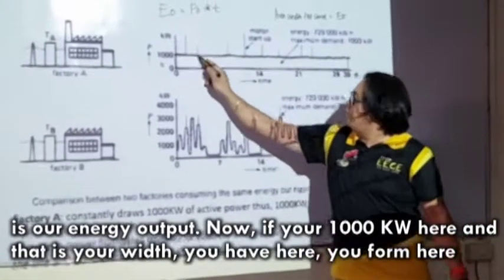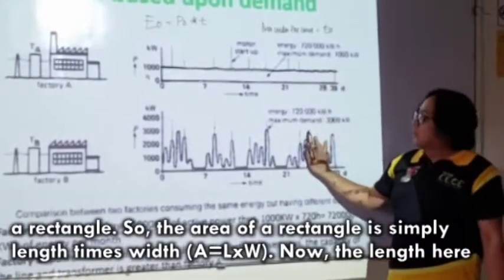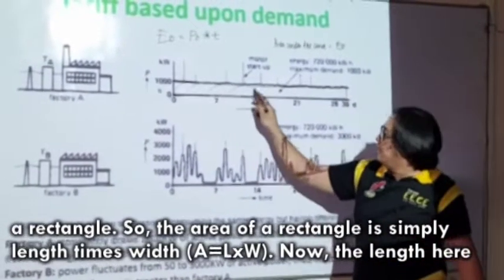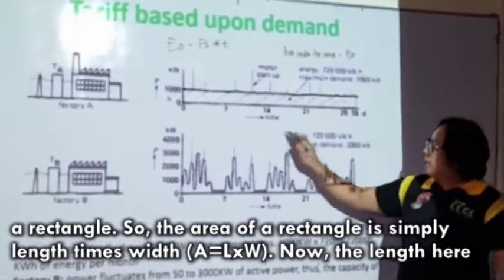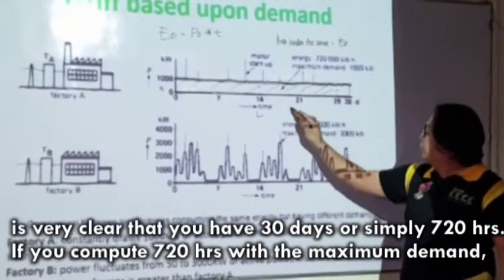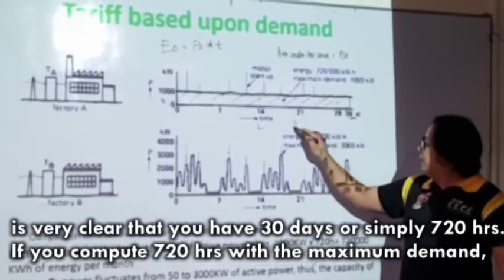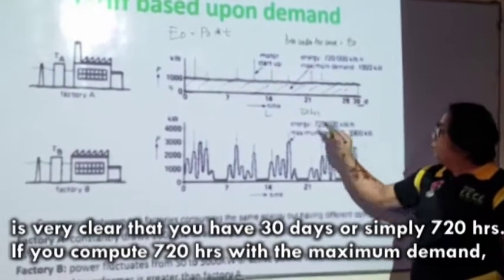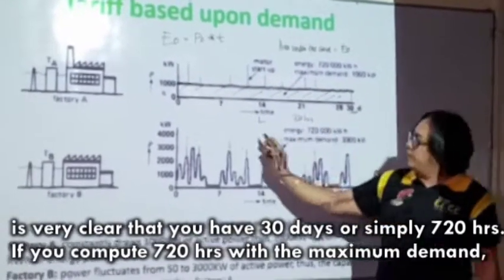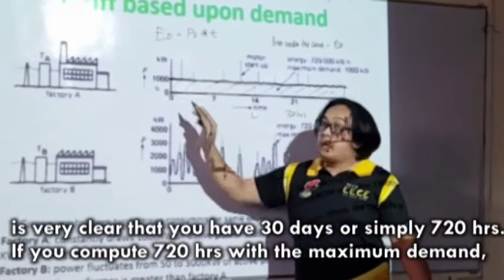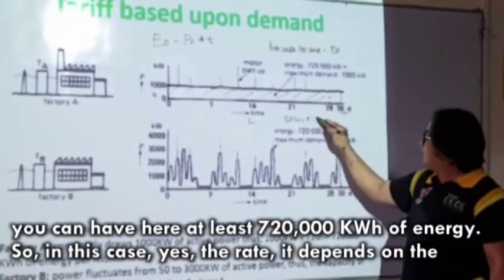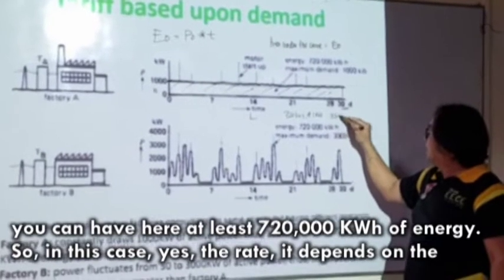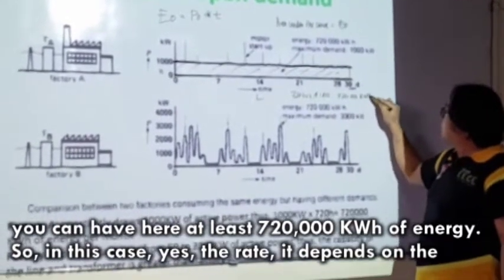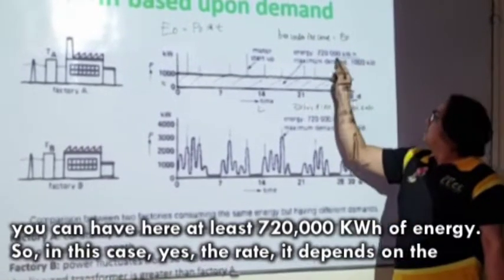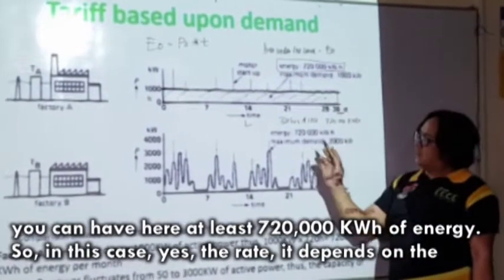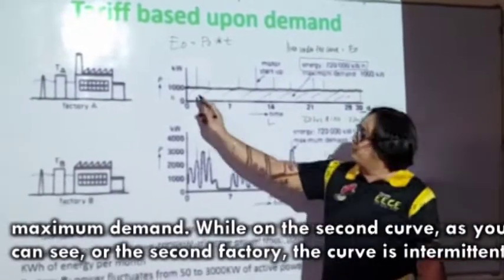Now, if you have 1,000 kilowatts here, and that is your width, you form a rectangle. The area of a rectangle is simply length times width. The length here is very clear: you have 30 days, or simply 720 hours. If you multiply 720 hours by the maximum demand, you have 720,000 kilowatt-hours of energy. So in this case, yes, the rate depends on the maximum demand.